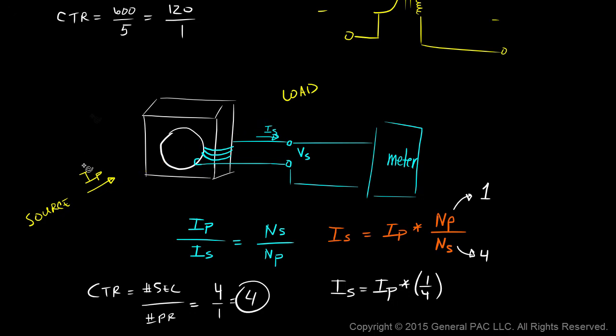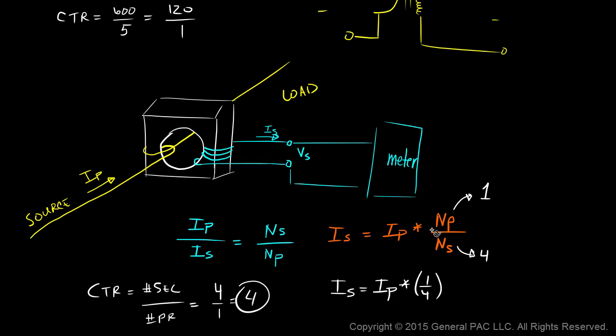Now suppose we remove the conductor and wrap it around the CT instead of passing it straight through. By wrapping the conductor around the CT, we have changed the number of primary turns — instead of 1, it is now 2. The number of secondary turns stays the same at 4.